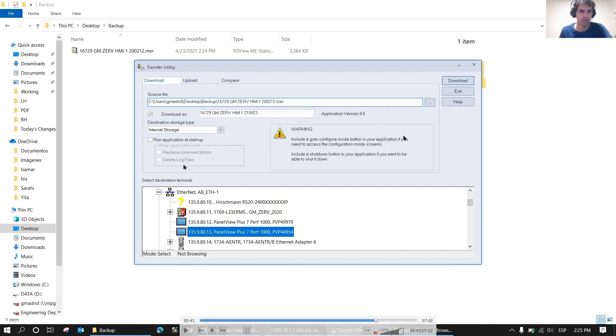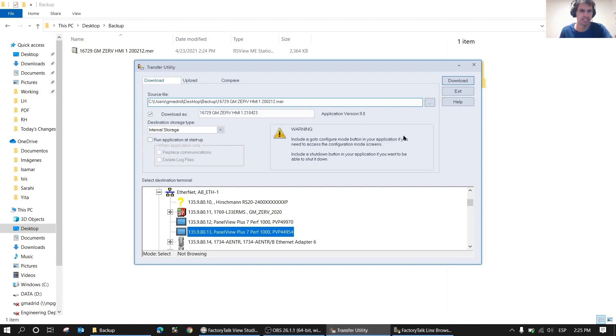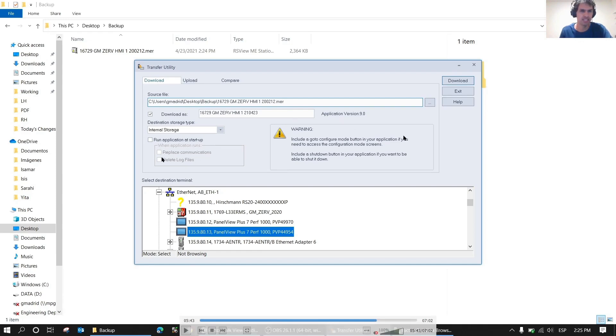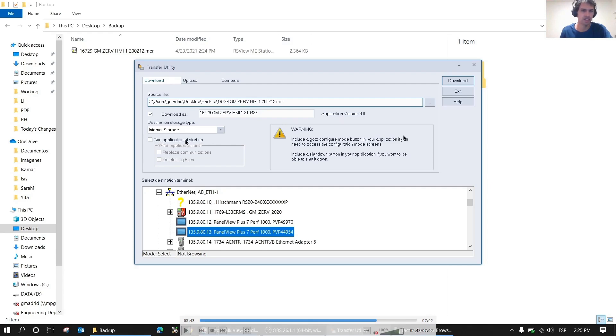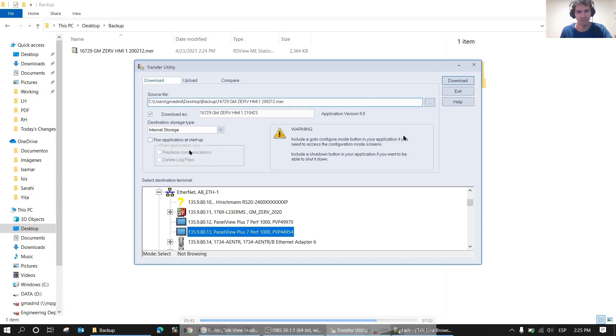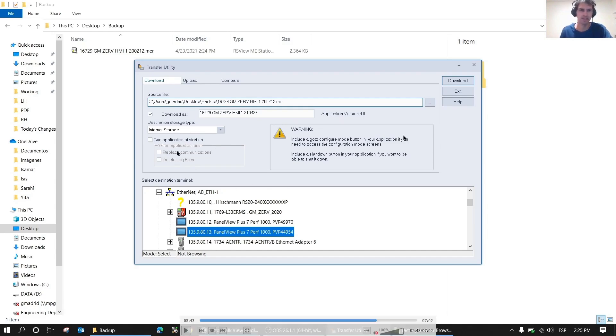I can also comment a bit here about replace communication. This means you're going to replace the communications of the running HMI with the new communications configured in this other HMI. So I generally don't click on this one either when I happen to click on run application at startup. It's rare for me to click on it because generally the application is already running, it's already working correctly, and if we're going to replace it, it might ruin what's already working unless your HMI is perfect. So personally I don't do it, but there are people who do.